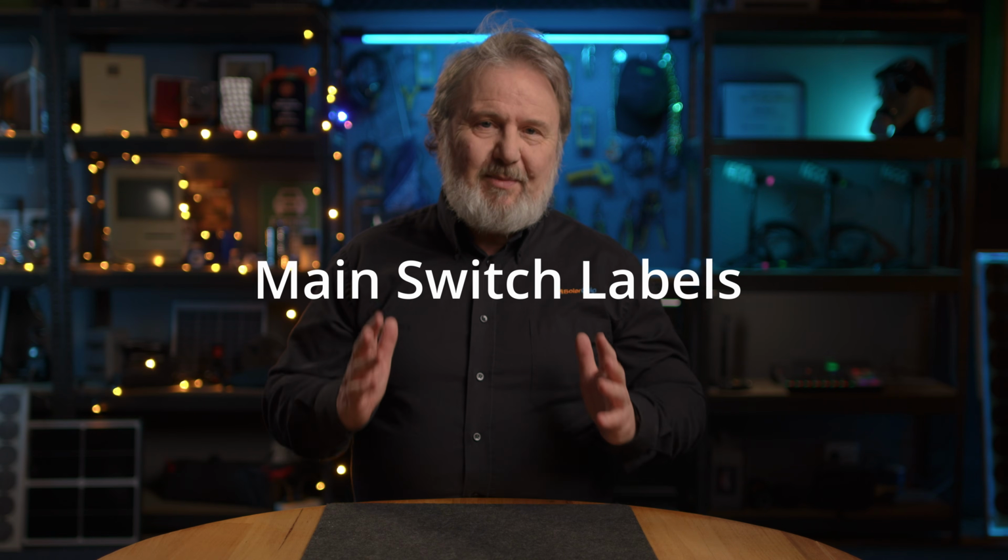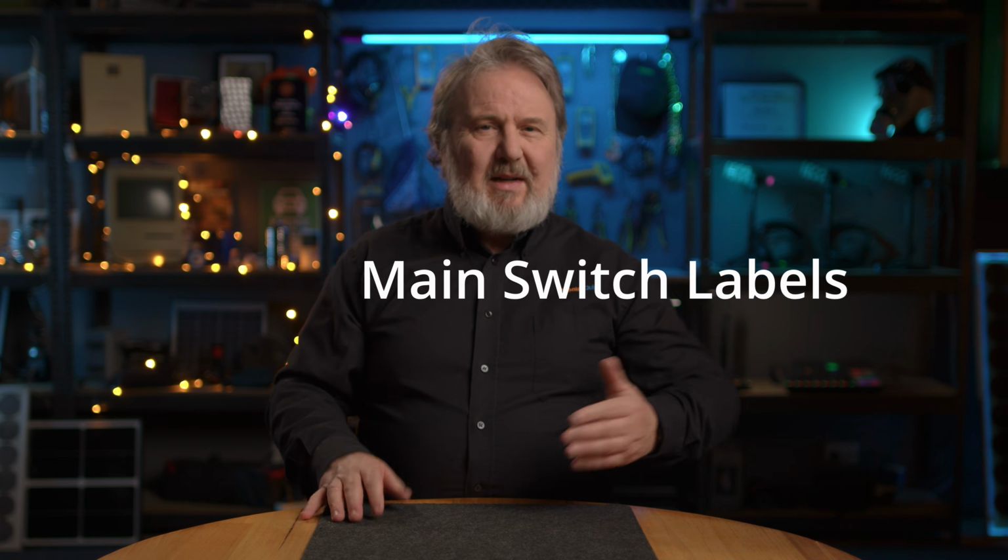Now today, it's going to be a slightly deeper dive, but just into one topic, all about inverter energy system labeling. Yep. So first up, there's a lot of new main switch labels. Some of you may have noticed that the standard has shown them with red lettering on a white background. What's that all about? Well, it's not prescriptive, but it's just one way of meeting AS/NZS 3000's clause 2.3.3.5a. It requires main switches to be distinguishable from other switchgear. Yeah, so colour is one way of achieving this.